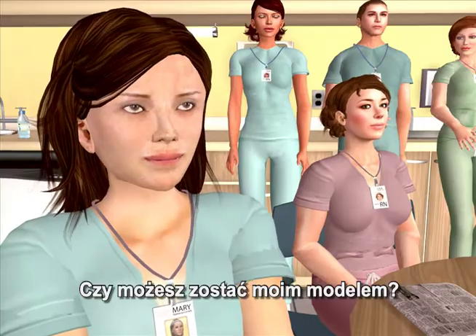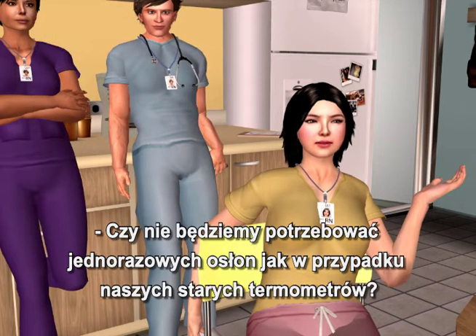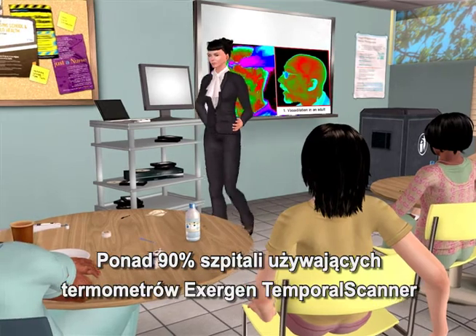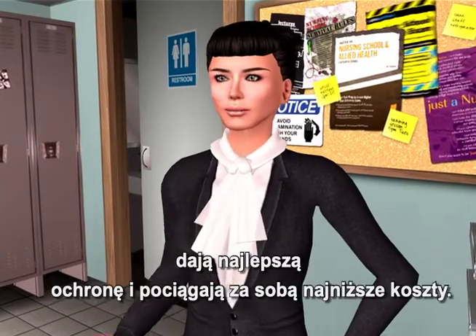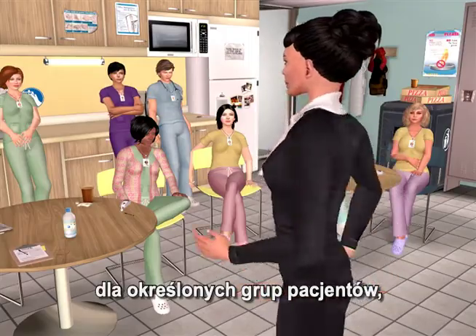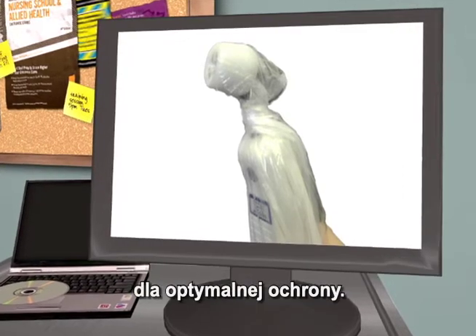Depending on the patient, you would first wipe the probe head with an alcohol prep pad, as you would with your stethoscope. With the temporal scanner, you are not contacting any mucous membranes, so in most cases, covers are not required. More than 90 percent of hospitals using Exergen TemporalScanner thermometers have approved wiping with an alcohol prep pad. Should the hospital prefer additional protection for certain patient populations, we offer disposable caps, which can be reused on the same patient, and for isolation patients, a long tubular sheath that encloses the entire thermometer for optimum protection.